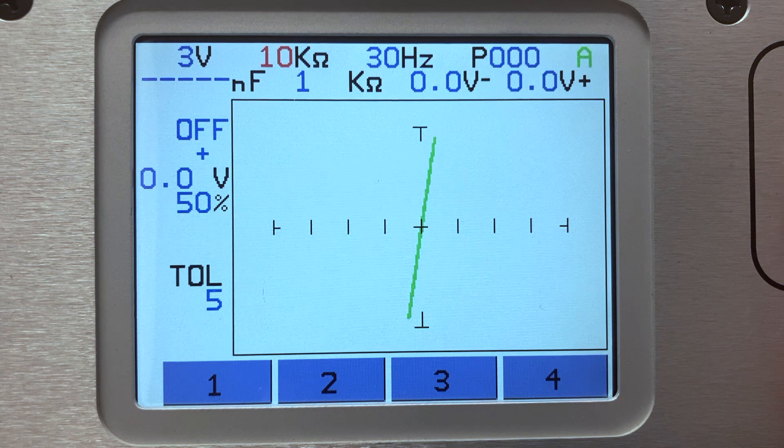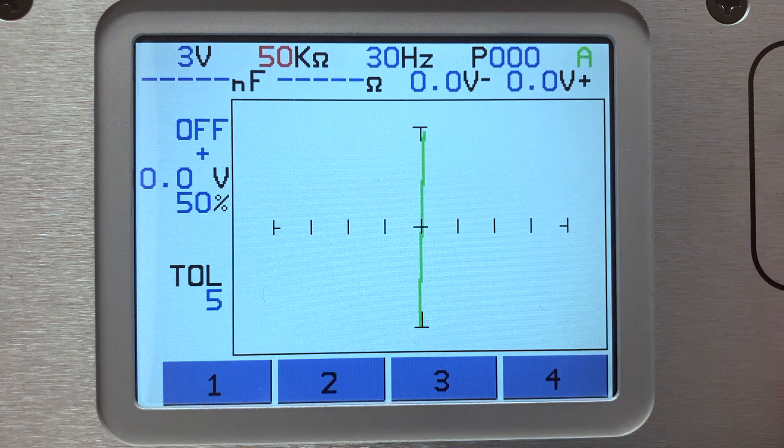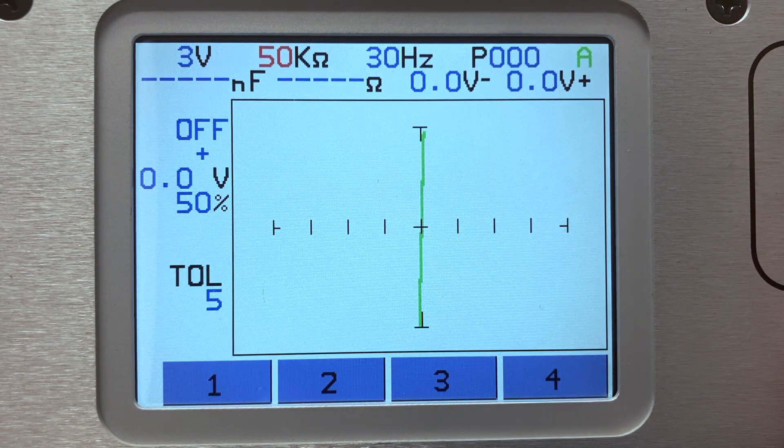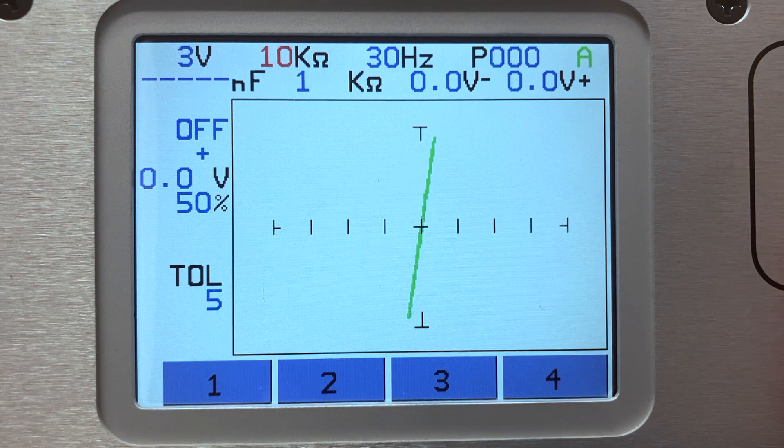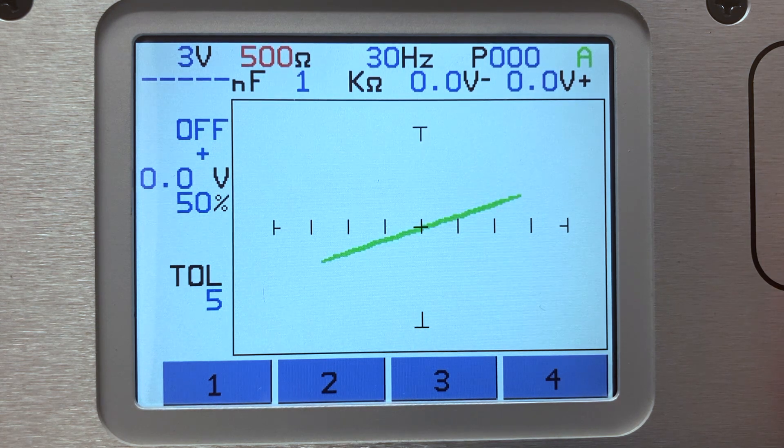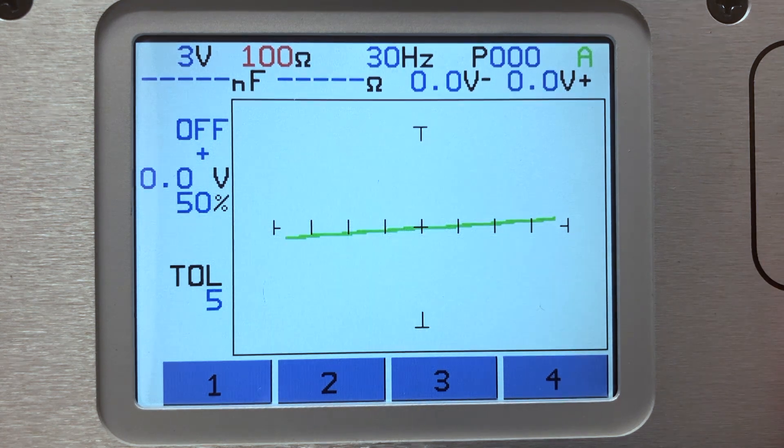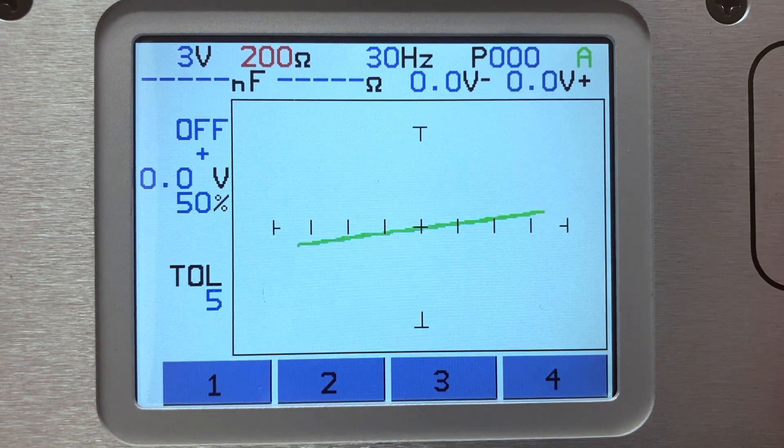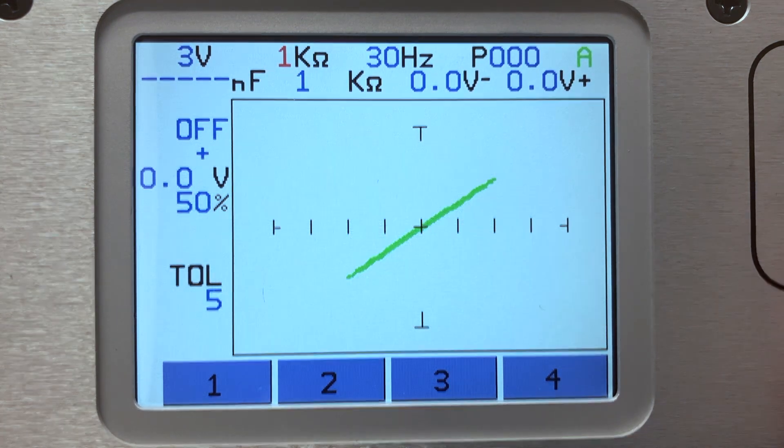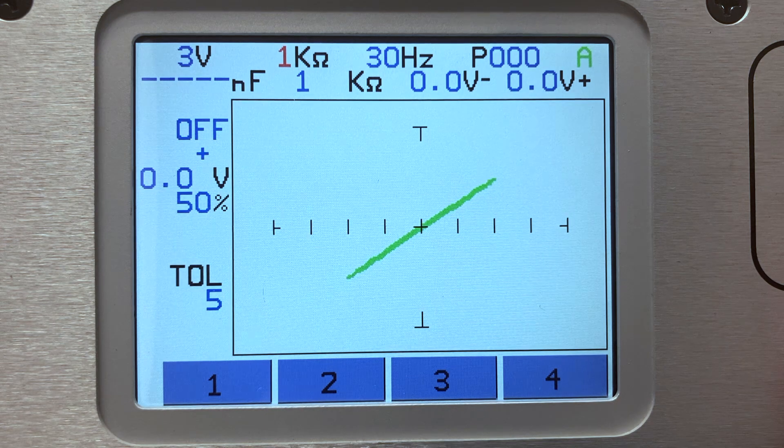Testing the same 1k ohm resistor in the 50k ohm range displays a more vertical signature angle. Changing the range lower to a 100 ohm range displays a more horizontal signature. The idea is to find a range setting that provides an equal amount of horizontal and vertical deflection in the signature.